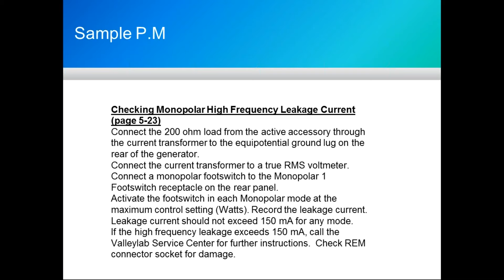You activate the monopolar foot switch, and the point here is you want to make sure the leakage current does not exceed 150 mA for any mode. If the high frequency exceeds 150 mA, call the Valleylab service. Since we're biomeds, we can also always go in and start fixing it ourselves or checking out the possible problems, such as the REM connector socket for damage.